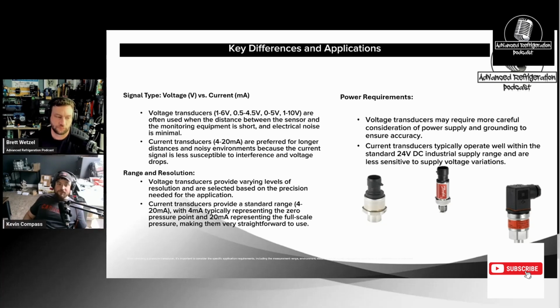And your voltages, because you need not just the voltage of the signal—it could be voltage, voltage drop, or milliamps. But you also need to know the resolution as far as the pressure, like 0 to 100, 0 to 200, 0 to 400, 0 to 650, 0 to 2000, whatever. And then the last thing you need is the power requirements.